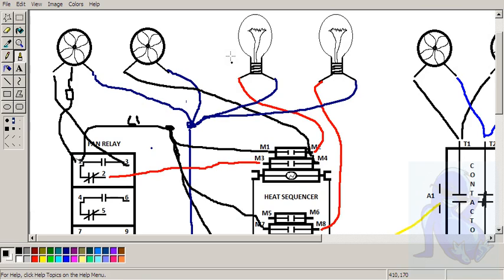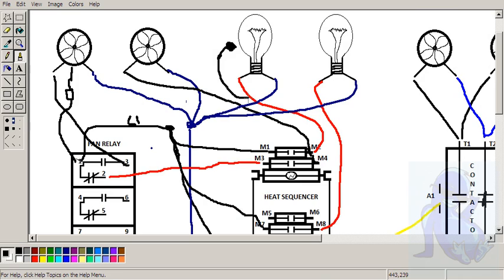You can also hook up all kinds of safeties on the system. We can put a safety sensor in here that senses how much heat we're putting out. And we could design that to say, hey, if that's getting too hot, I want it to shut off the power. And it will break that line. It will stay closed unless that hits a certain temperature. And then it will pop open because it senses too much heat.